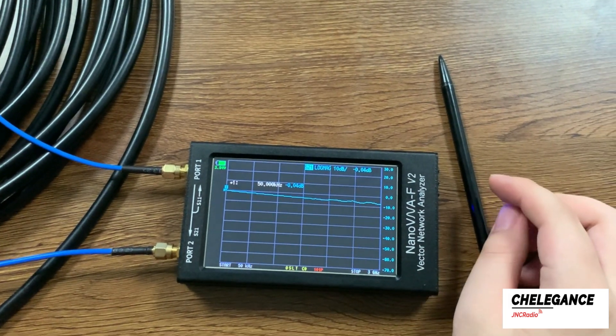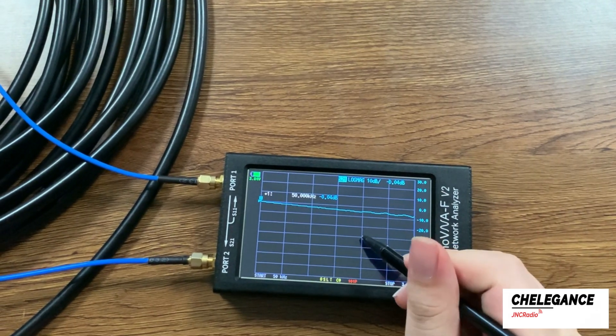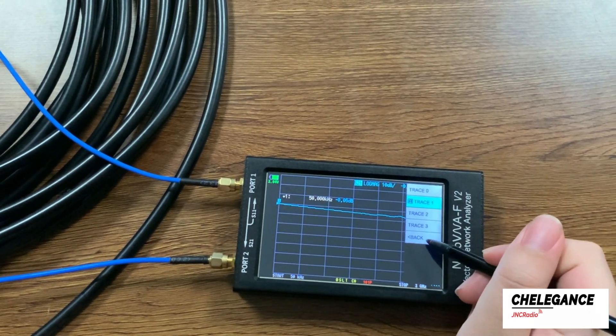Once connected, what appears on the Nano VNA screen is the insertion loss of our cable at different frequencies.